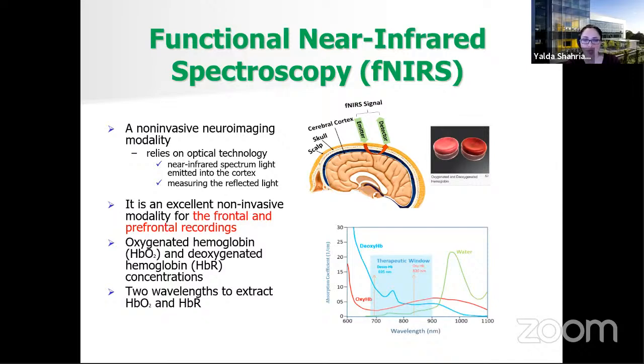It provides the hemodynamic changes similar to what functional magnetic resonance imaging, or fMRI, does, but fMRI has much higher spatial resolution. However, it's much more bulky and more expensive compared with fNIRS. So this technique takes advantage of the optical window in which the bone, the tissue, and the skin are transparent to near-infrared light, which is between 700 to 900 nanometers. It is an excellent candidate to record from frontal and prefrontal areas important for executive functions. It works based on two wavelengths to extract oxygenated and deoxygenated hemoglobin levels.